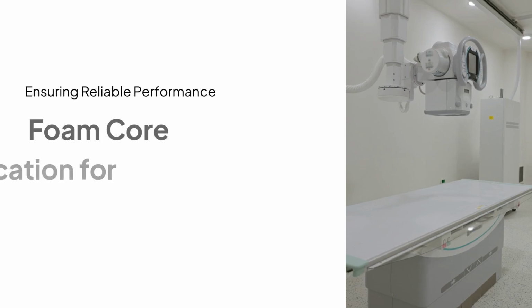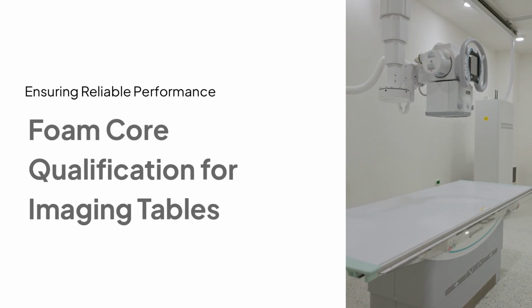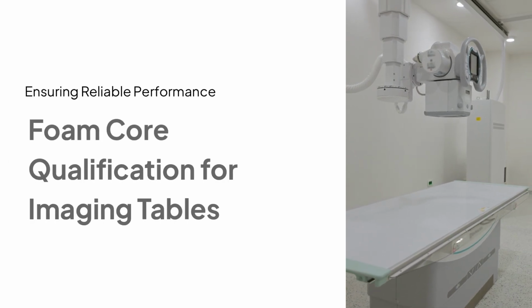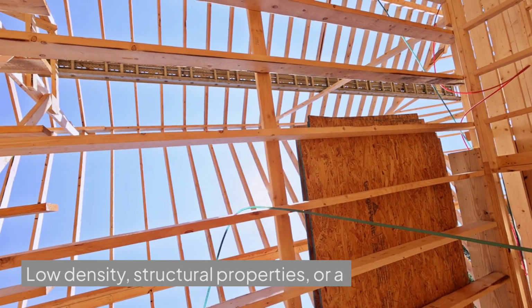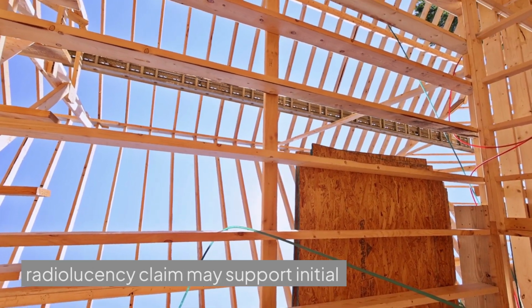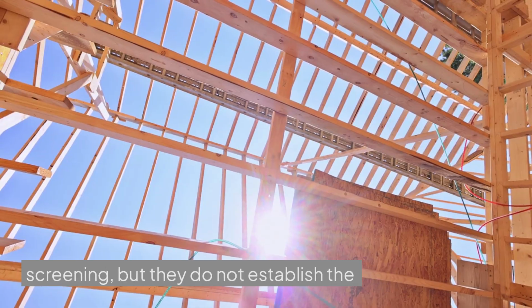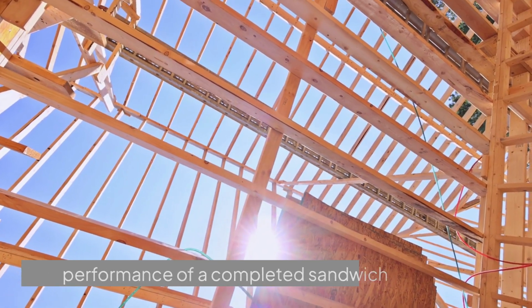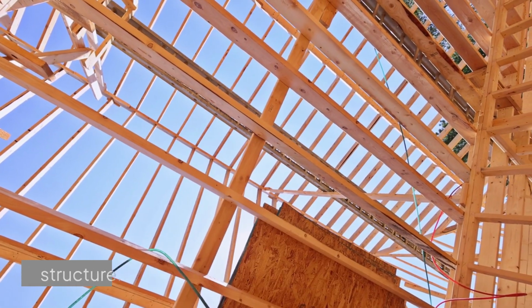A foam core can look ideal on a datasheet and still fail the application once it becomes part of an imaging table. Low density, structural properties, or a radiolucency claim may support initial screening, but they do not establish the performance of a completed sandwich structure.